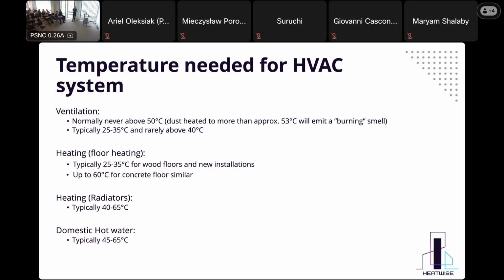If we have floor heating, low temperatures, 25 to 35, that's what you saw in the EMPA case. You can of course have higher temperatures, but typically there's no need if you have a sufficiently insulated building. Radiators, typically in Danish conditions, 40 to 65, and that may depend very much on when your building was erected. If we go back to 50-year-old or older buildings in Denmark, they're typically designed for maybe 90 degrees, so it depends on the age of the building and heating system.